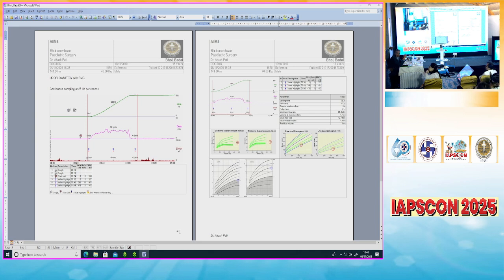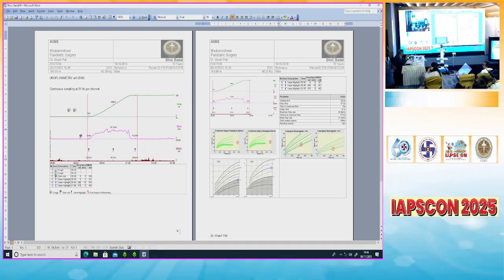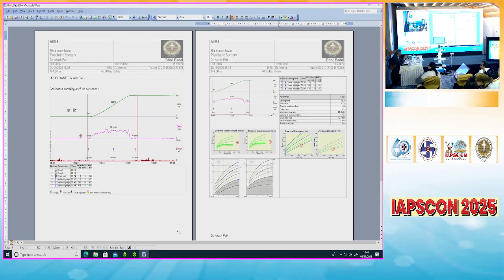So you see, there is a sphincter activity before starting, which with the command becomes low, and after that it again gains the baseline EMG activity. So this is an ideal curve, which is a good curve. I mean, all criteria are satisfied. We can call it bell-shaped, and most important is this range. This range is from 0 to 50. I was telling you, this same curve, if I make it 0 to 10, it will become a tower curve. And if I make it 0 to 100, it will be a plateau. So it's very important. Normally in uroflowmetry, we keep the range at 0 to 50.